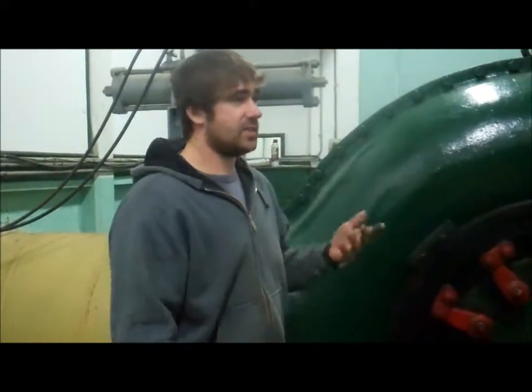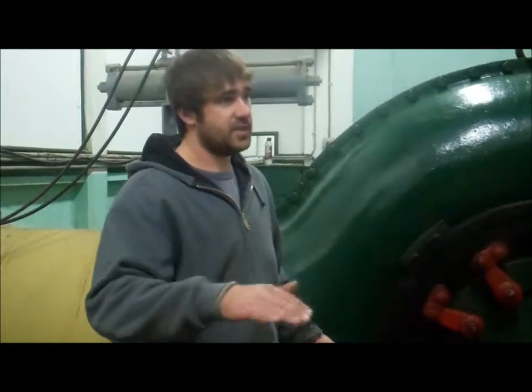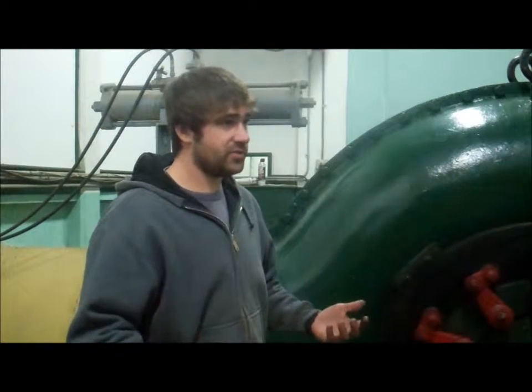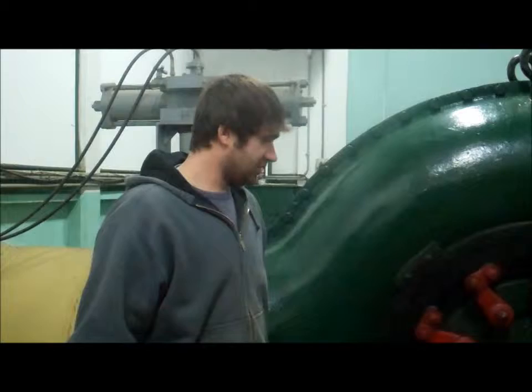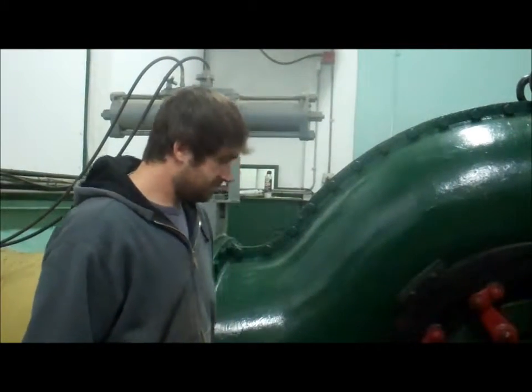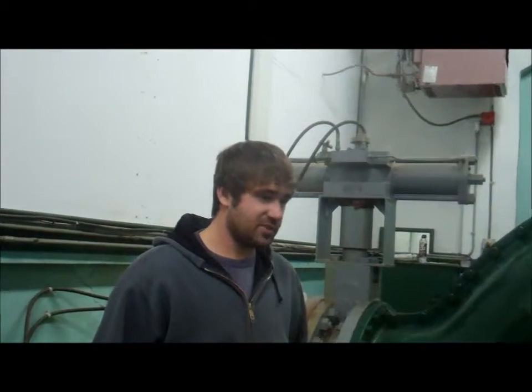If there's anything that goes out of the norm in their preset settings, it'll set off an alarm, it'll call my phone. And then if I don't get here in time and it keeps getting worse, or it's getting hotter, or something's going on, the computer will take over and start shutting down machines. So it's a pretty good system.